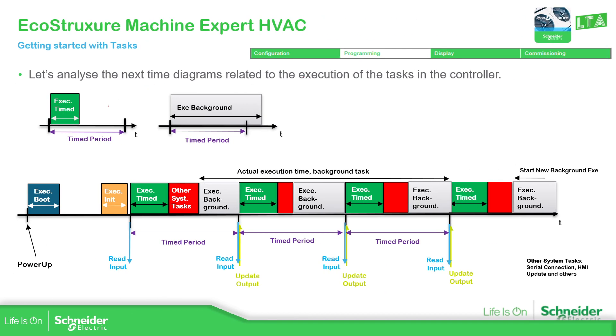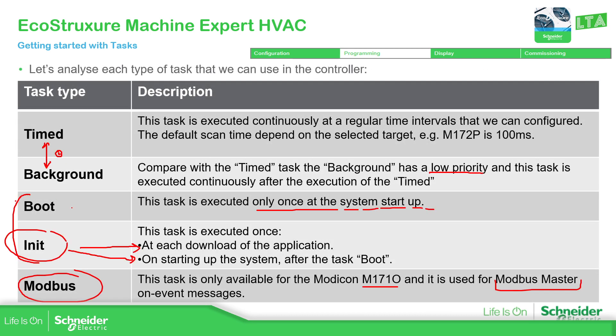This diagram shows the period of the time task execution. You can see the configured time for the time task and the execution of the background. The background extends beyond the actual configured time period. The execution time of both time and background depends on the code we have. As soon as the M171 or M172 powers up, it first activates the boot task.